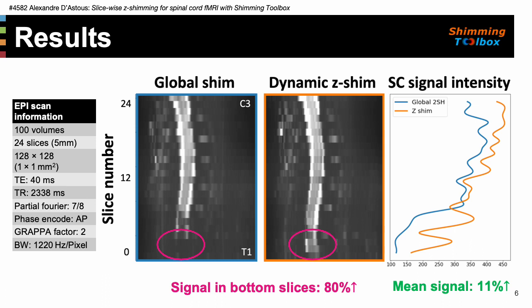We also observed an increase of 80% in signal intensity in lower slices, a benefit of the slicewise shimming that changes the shim coefficients for each slice.